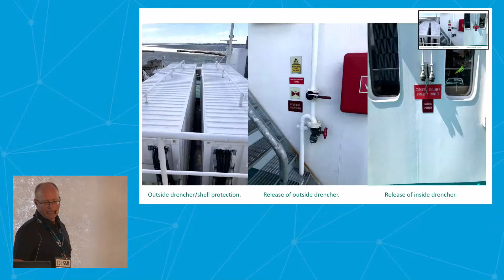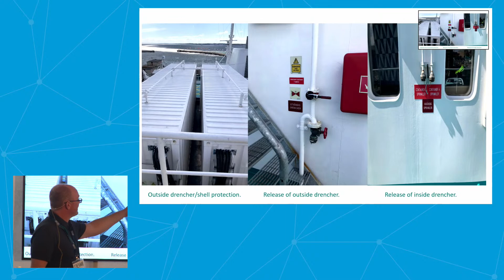On the outside, we have different options. We have a drencher shell protection in case we have a fire in the accommodation and that will spread. The heat will go inside the containers. So that's a normal case. You always start the shell protection outside the containers and protect them from the heat. And you can also then connect separately the inside drencher, but it's not always connected. It's like a safe thing, so you don't make any mistake. You have to think a little bit more before you connect the hose and start the inside sprinkler.